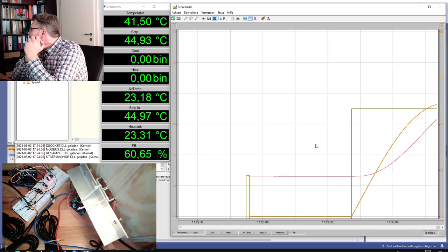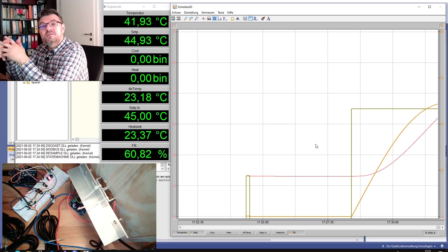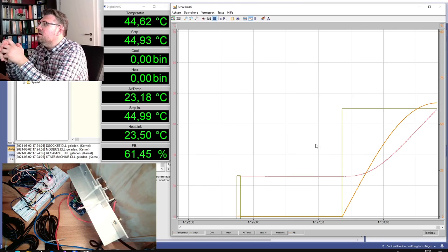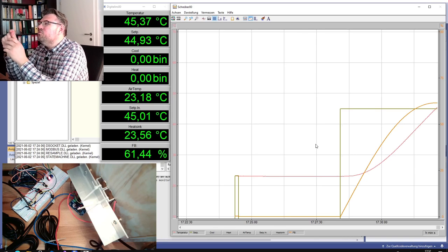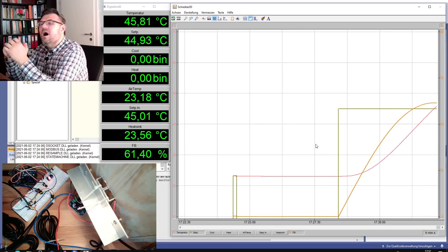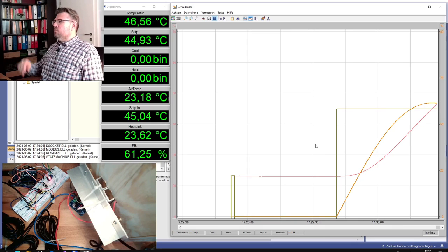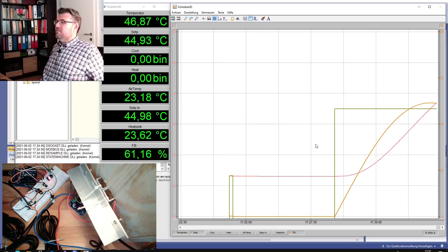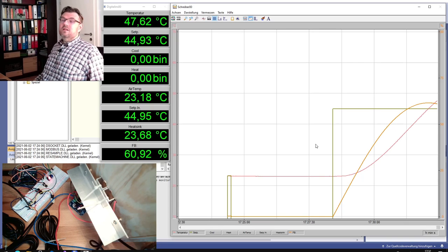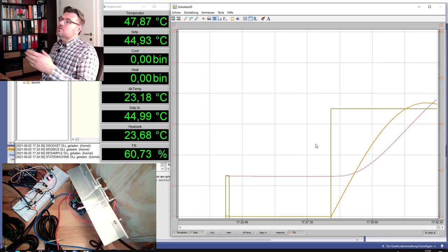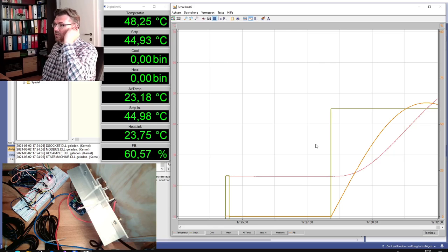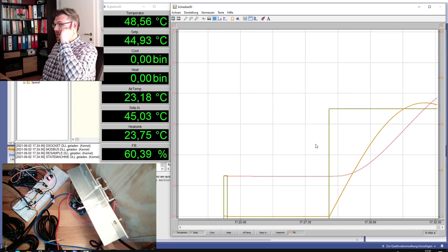However, it's still growing, because we are still approaching the value. And now we are beyond the value. And now we'll start to decrease. Now the I controller finally realized this was too much, so it will go down again with the heating. Now the controller deviation is in the other direction, so it will go down, but also not too fast, because the deviation is not that big. We will see a huge overswing there.